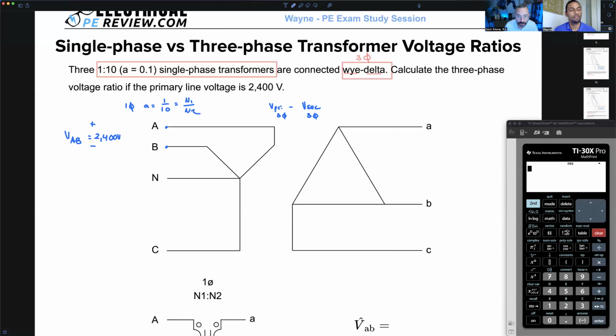I'm going to draw a winding from A to B. Here's the primary winding for one of the single phase transformers from capital A to capital B, and then the secondary winding would be from lowercase a to lowercase b on the delta side. Together, this makes one of the single phase transformers inside the overall three phase transformer.